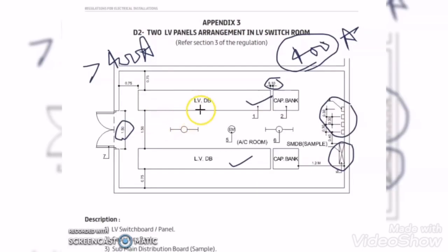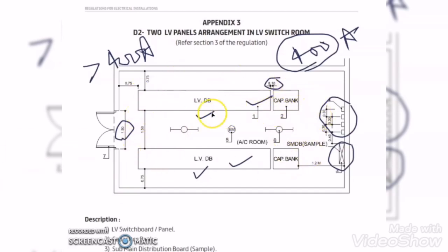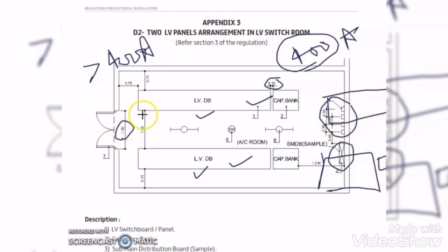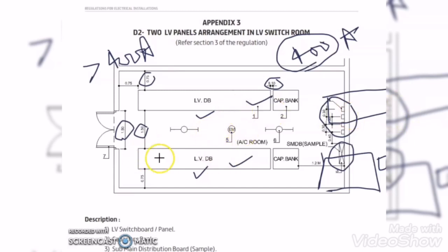You might have a question: suppose your building requires 4 LV panels — what is the DEWA regulation for more than 2 LV panels? We follow the same approach: place the LV panels and capacitor banks in the same manner, maintaining a panel-to-panel distance of 1.5 meters and a distance of 0.75 meter from the back side of the panel to the LV room wall. Even if you have 6 or 8 LV panels, you place them in the same manner by maintaining the minimum distances.